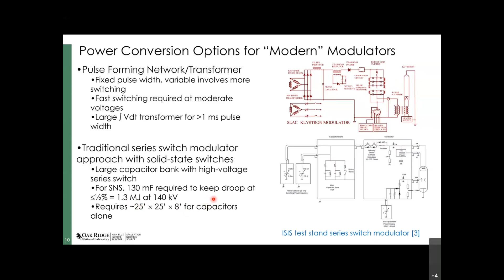The problem with the SNS application, since it's a long pulse application, is that to have minimal droop with this technique we'd require a very large energy storage capacitor bank, in this case on the order of 1.3 megajoules, which is quite large, occupying floor space of about 25 feet by 25 feet. So that was not very practical for us.